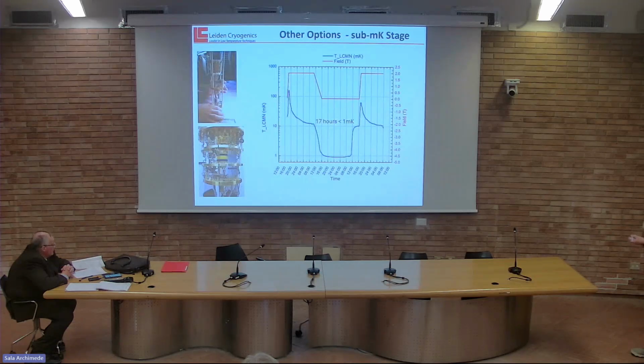As another option, if base temperature of 10 millikelvin, 8 millikelvin is not enough, we also offer nuclear demagnetization stages. It's not continuous, it's a single shot process, but you can actually go below 1 millikelvin for hours if you need it. So in this case, for instance, this is the system we developed for Leiden University. It was under 1 millikelvin for 17 hours, and then the technician came and bumped into the cryostat. It warmed up. Otherwise, it would have stayed even longer.